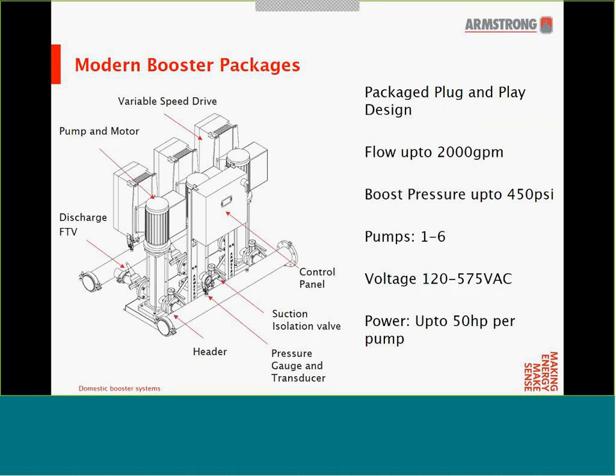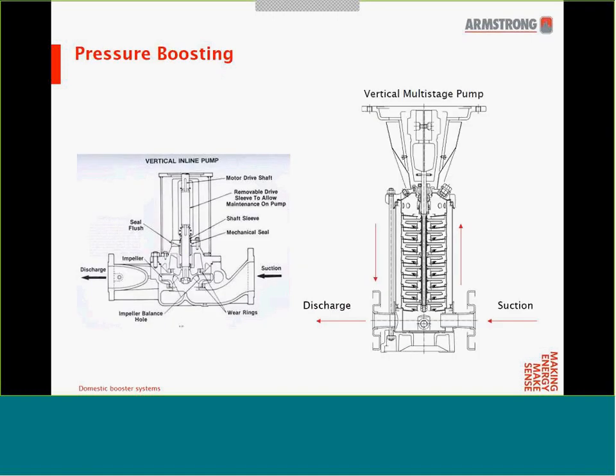Typical booster capability includes flows up to 2,000 GPM, boost pressure up to 450 PSI, number of pumps ranging from 1 up to 6, voltages from 120 volts up to 575 volts, and power up to 50 horsepower per pump.